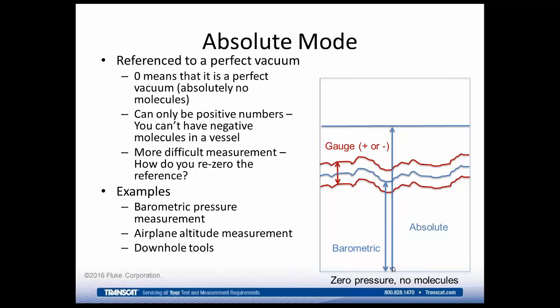Absolute pressure is referenced to a perfect vacuum. So that's where one end of the line is down at 0, and so this blue line up at the top is an absolute pressure, and shown in this case to be a stable absolute pressure. So if you have a reading in absolute mode and it says 0, that means it is a perfect vacuum. If it's 0.00000, that's a perfect vacuum. Absolutely no molecules in the system, no pressure whatsoever. That's kind of a theoretical point because it's extremely difficult to get every single molecule out of the system, if not impossible.